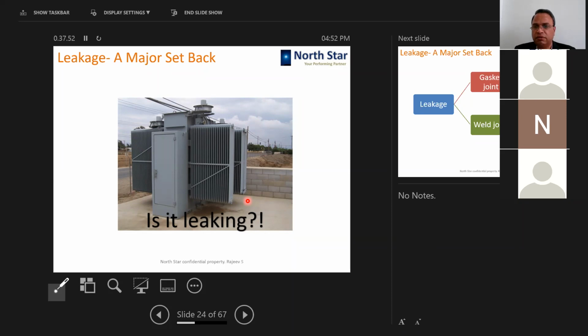But I will tell you, the gasket, when it starts leaking, you cannot arrest it by tightening it. I have been saying this so many times, once the gasket is set in a groove or in a joint, it has taken its shape. So whatever amount of tightening you can do, you cannot stop the leak permanently. It will slow down, it will stop for a while, but after some time it will come back with more vigor and more seriousness.